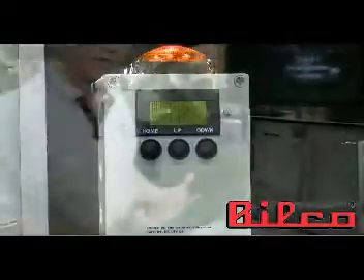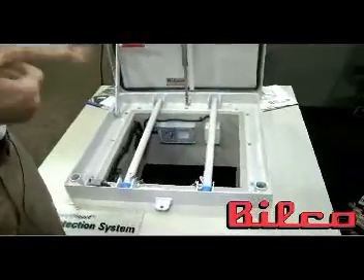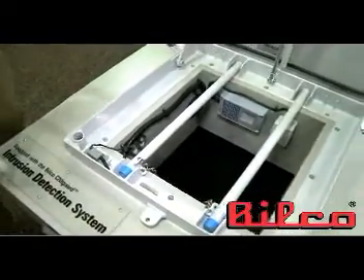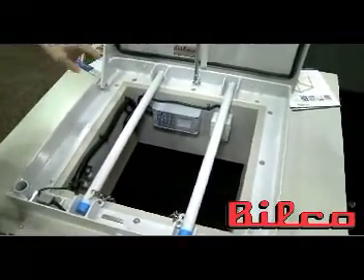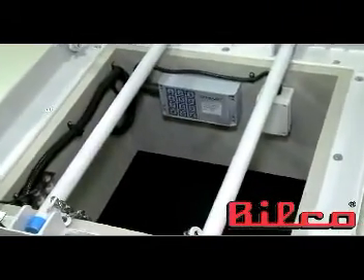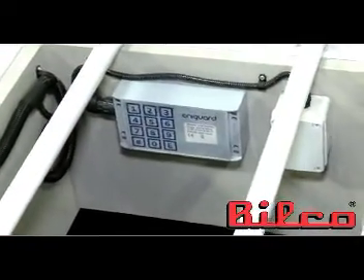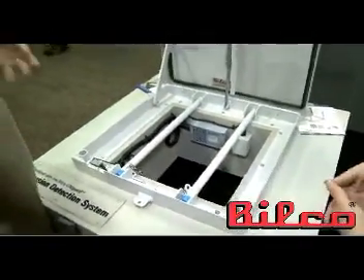So now they are alerted and know that someone has actually breached this hatch, and then they can respond in any way they wish. So one of the things that this does is detects the opening and closing of the hatch. The other thing that it does, as shown in that video, is if someone's cutting or grinding into it, it has seismic sensors inside this box, and it's able to detect whether someone has actually cut a hole in it. But critically, it's able to also make sure that it wasn't a nuisance or an environmental alarm, let's say like rain or hail. So it makes sure that you have a genuine alarm which is being sent.